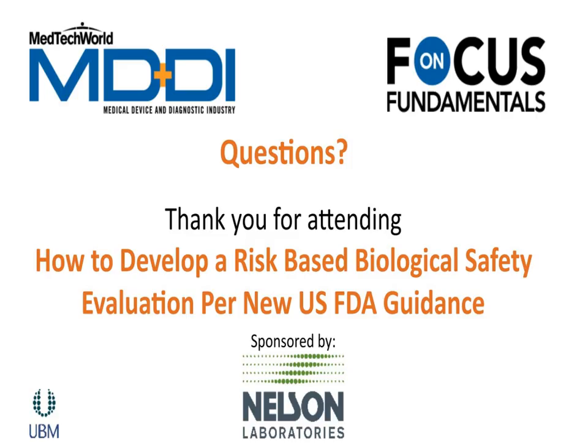Great. So a couple more questions. A gap is identified in the BER and now more testing is needed. How do I get this addressed without doing another BER? Yeah, you're hoping at the end that you don't find out about those gaps at the very end when you're doing your final conclusion. And so for our policy here, depending on the length of test, what we can do is just hold that BER and not complete that until you've done the testing and then add that in. So we would just keep your report as a draft form, and then when the testing was completed, add that in, make the conclusion, apply to that current testing that was done, and complete the report at that point.